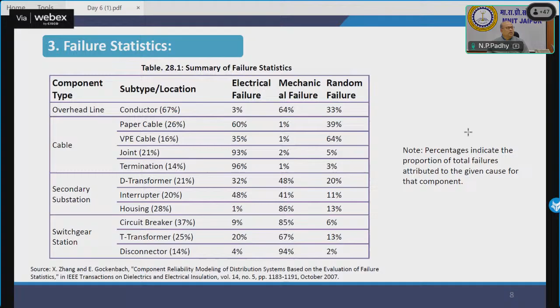For example, if I talk about transformers, 48% is going to be mechanical, 32% is going to be electrical. In case of switchgear, in case of circuit breaker, 85% is going to be mechanical failure. There is nothing to do with electrical here. Right? So the percentage indicates the proportion of total failure attributed to the given cause for that component.